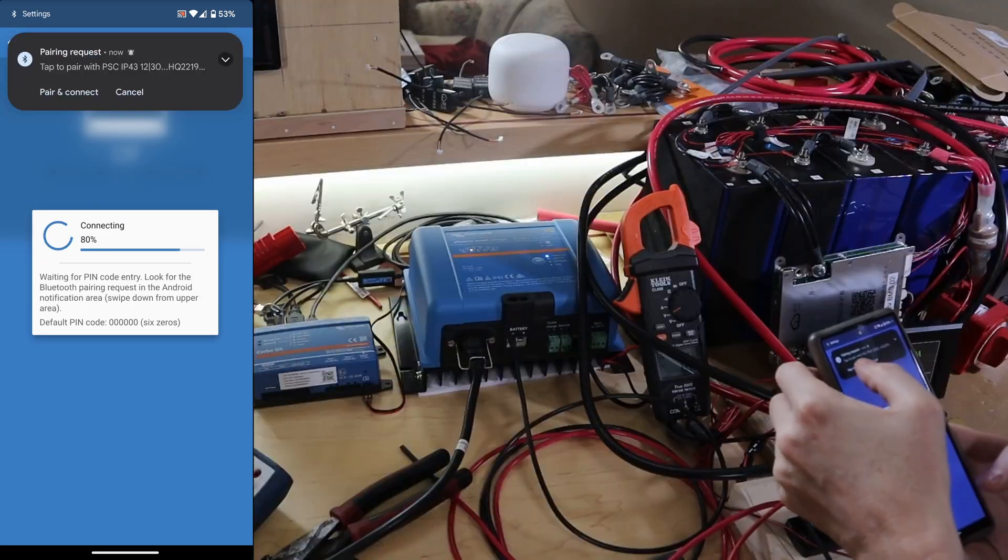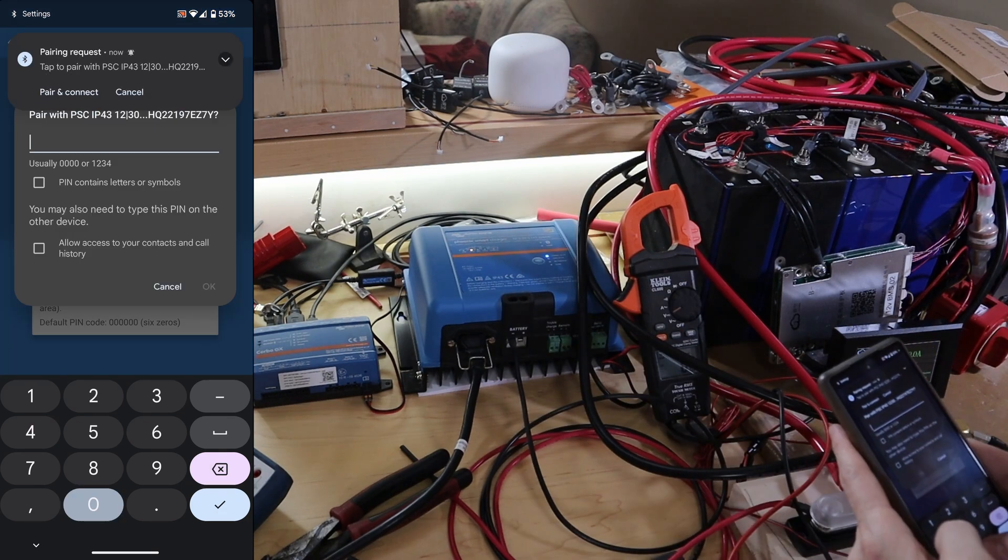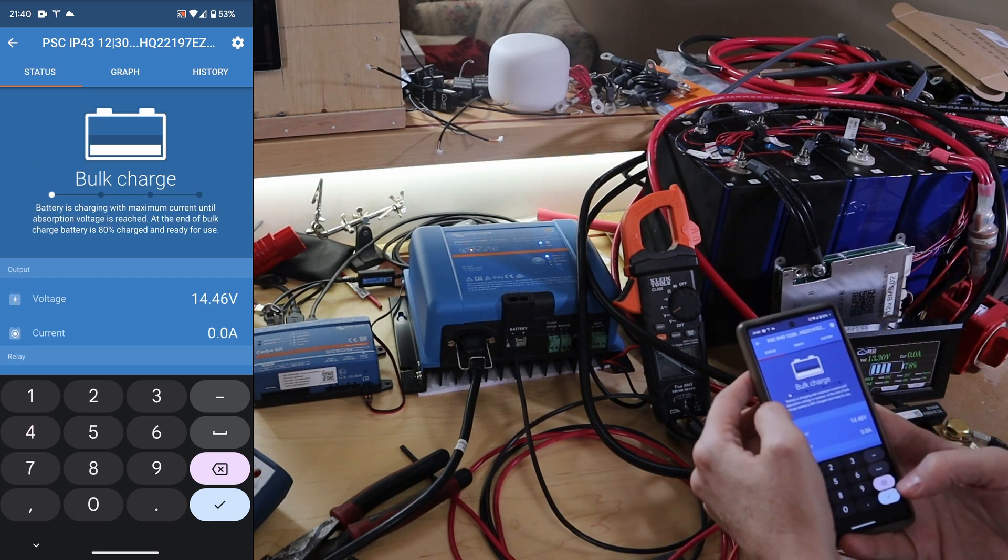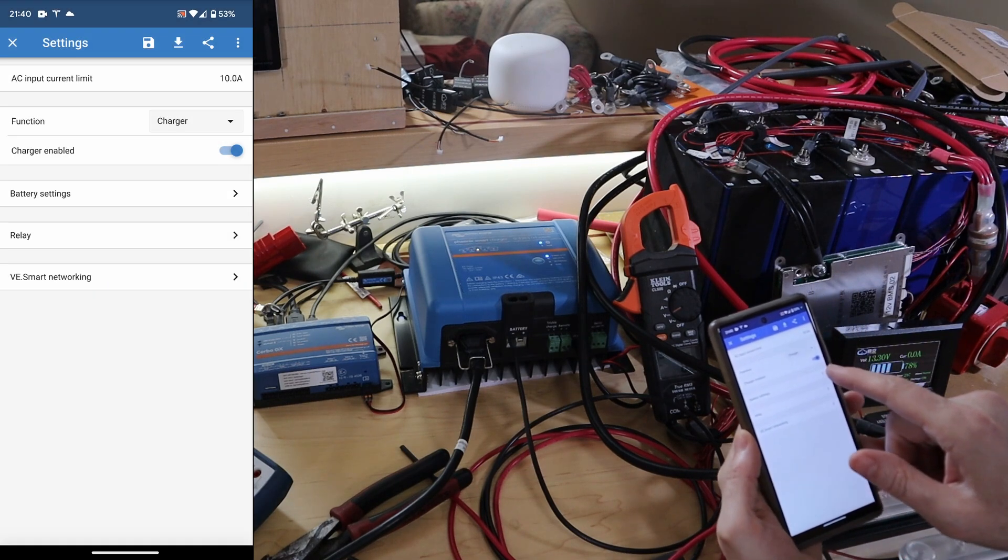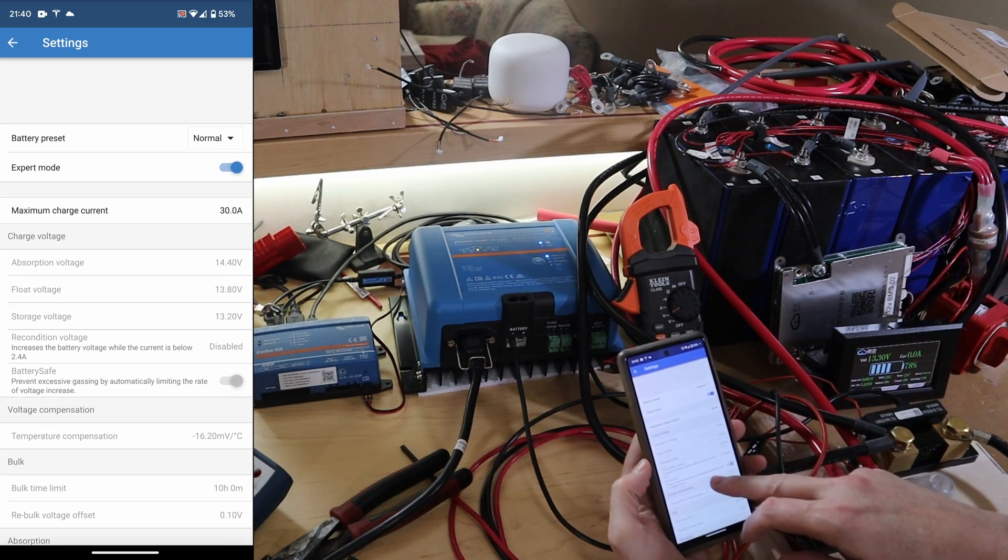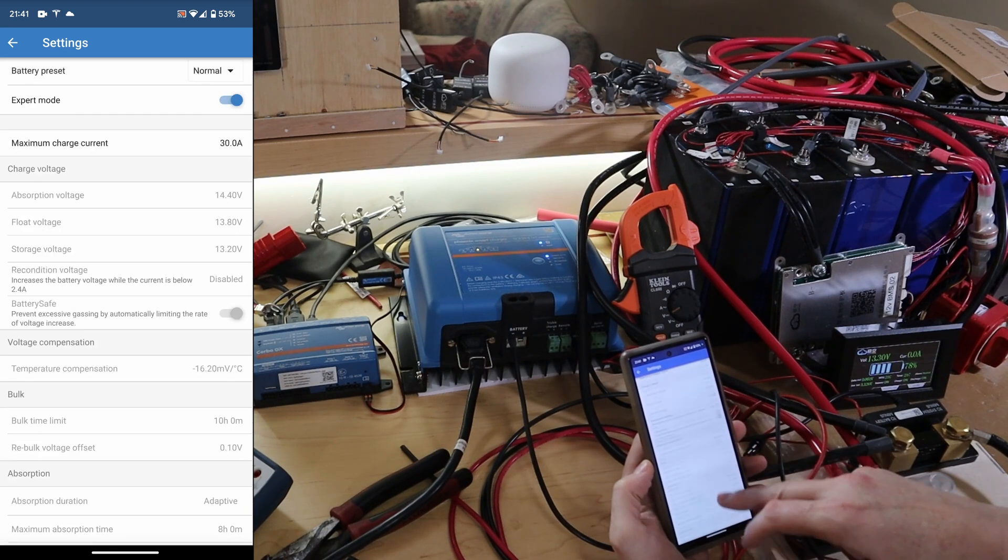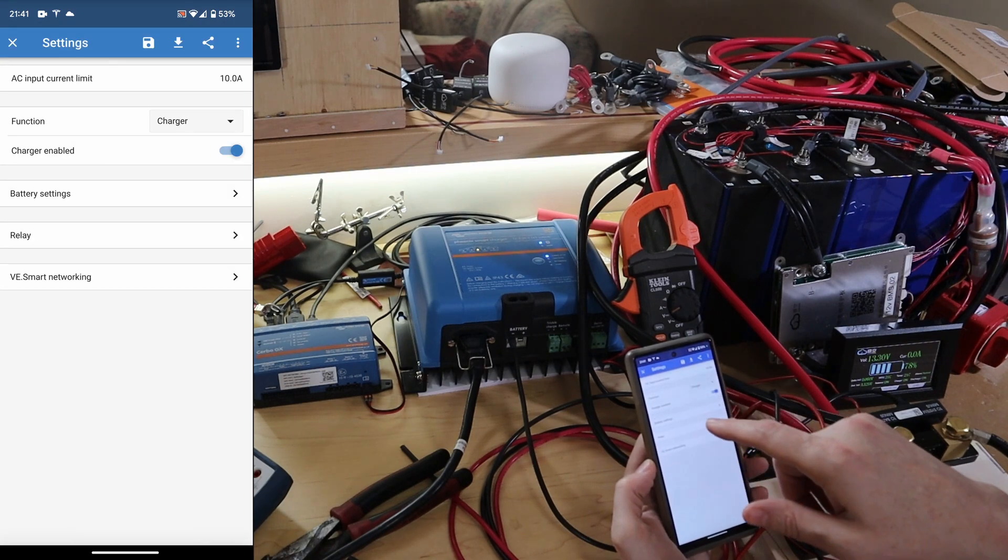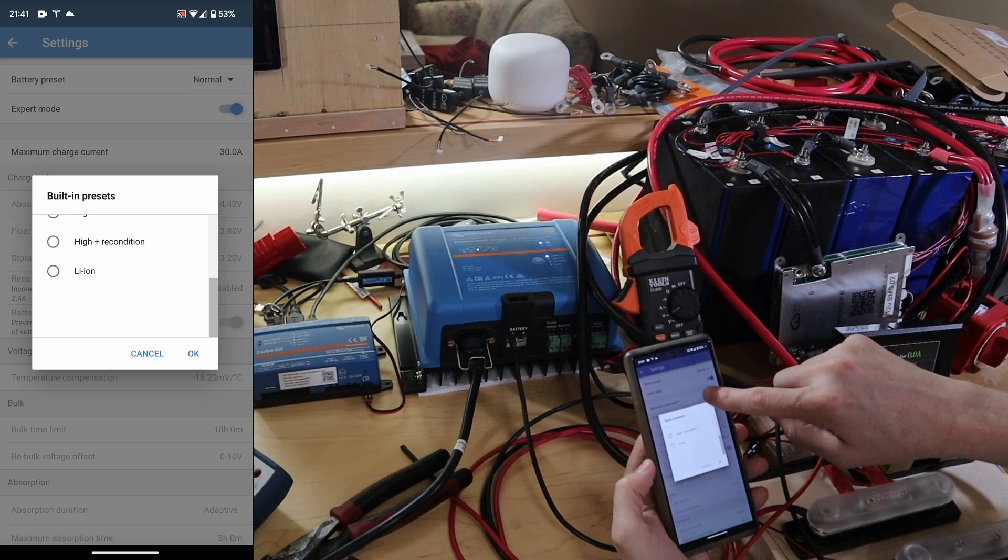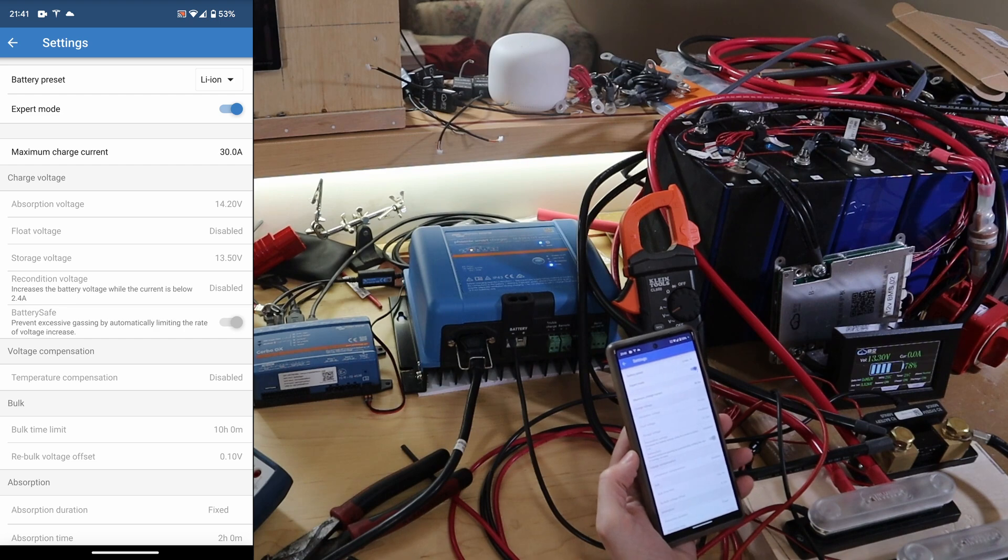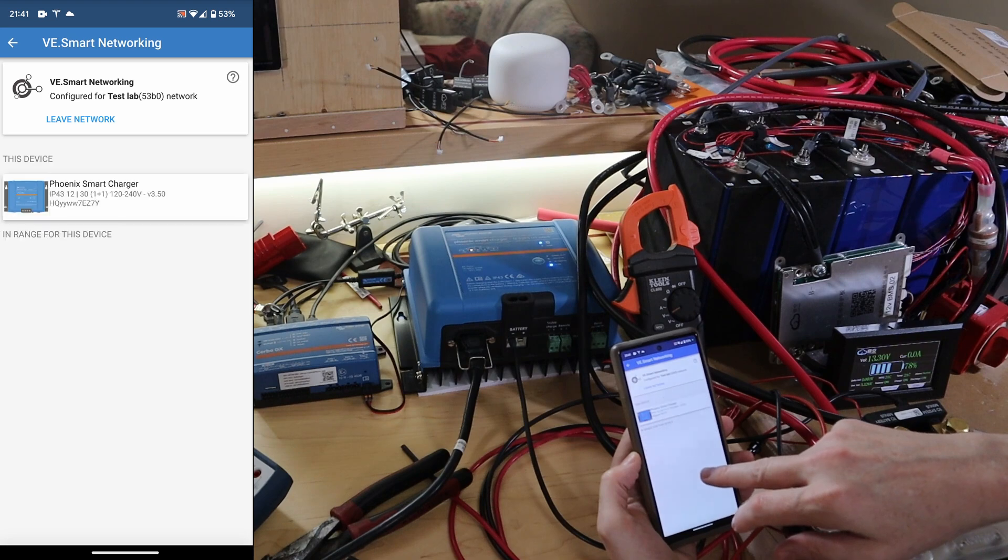It's doing a nice little light show. One, two, three, four, five, six. Here we go. Unsecured access. No, I'm going to do all those when it's actually on the boat. Maximum charge current is 30 amps. That's fine. That's what I paid for. I just need to make sure that the chemistry is set to lithium iron phosphate. Battery settings. Battery presets, built-in presets. Lithium ion. There we go. Down there. Now what they call lithium iron is lithium iron phosphate.